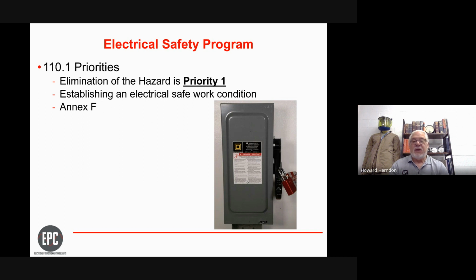One priority people fail to realize: for instance, with this safety switch, I've opened it to change fuses, but are there other risks and hazards associated with that? Sure there are. Most likely the line side of that switch is still energized. So now I've created an electrical hazard, and I need to go upstream of this device and do an appropriate lockout tagout, because changing fuses here creates exposure to an electrical hazard.